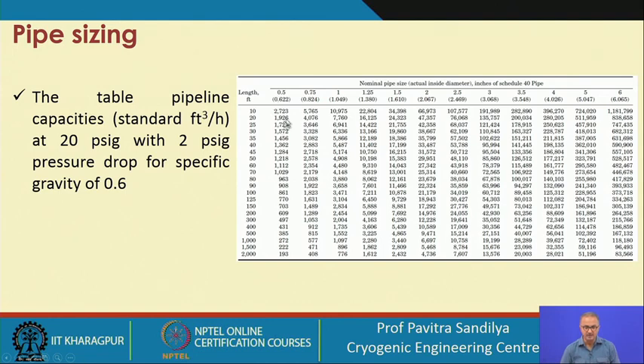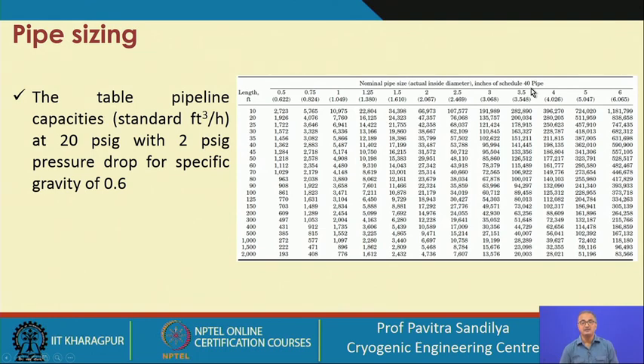This particular table gives various pipe lengths and nominal pipe sizes, showing the flow capacities in the pipeline. You will find this kind of table for different types of pipeline. The nominal pipe sizes are listed with the inside diameter in brackets — these are for schedule 40 pipe. The schedule number signifies the wall thickness of the pipeline, and combined with the nominal outside diameter, allows us to calculate the inside diameter.